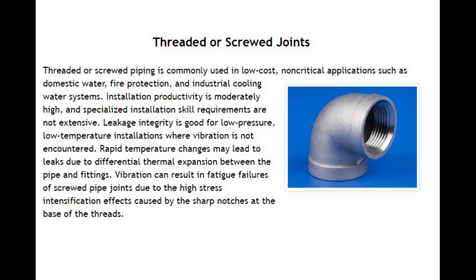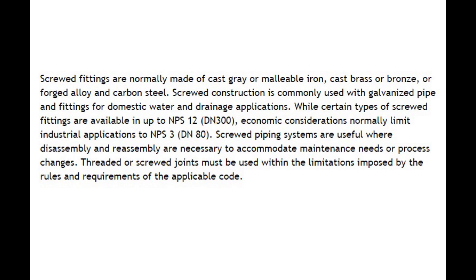Rapid temperature changes may lead to leaks due to differential thermal expansion between the pipe and fittings. Vibration can result in fatigue failures of screwed pipe joints due to the high stress intensification effects caused by the sharp notches at the base of the threads. Screwed fittings are normally made of cast gray or malleable iron, cast brass or bronze, or forged alloy and carbon steel.